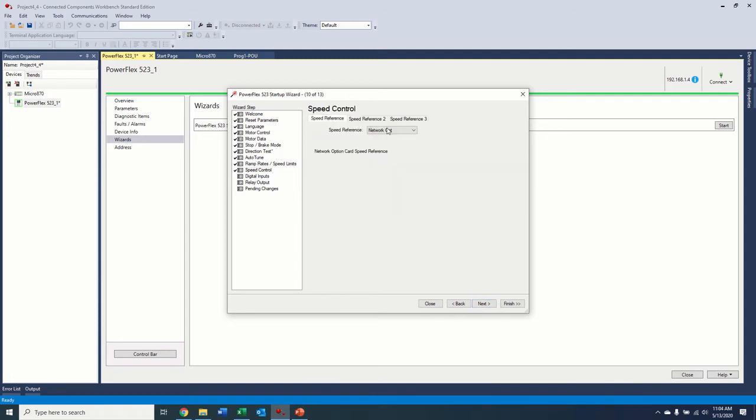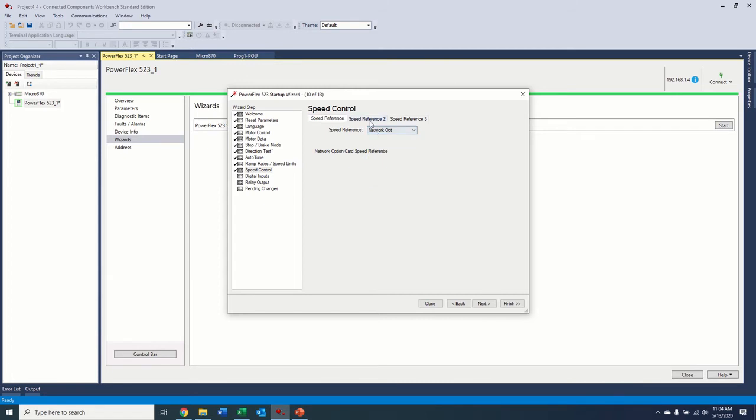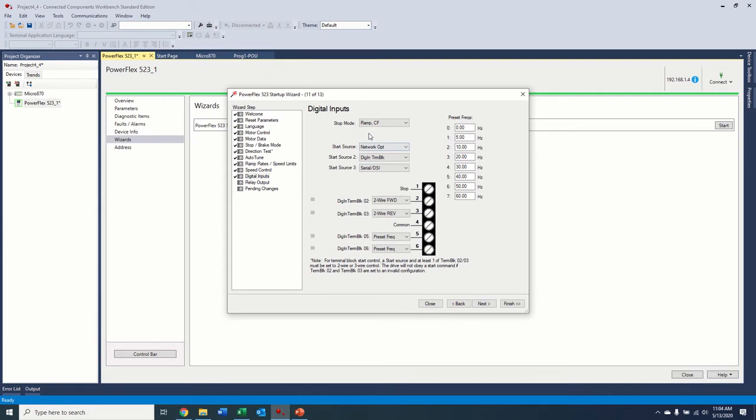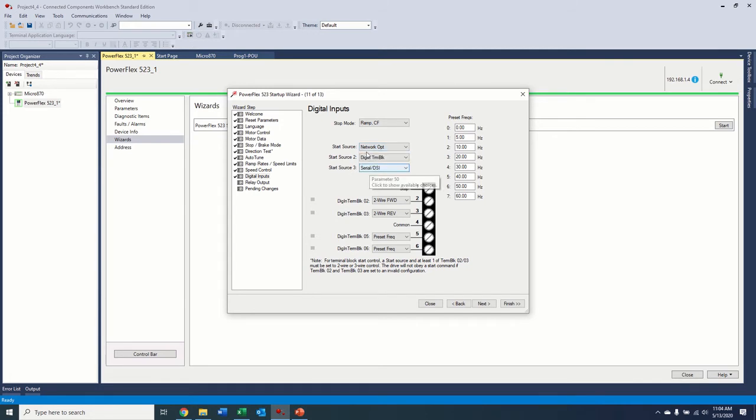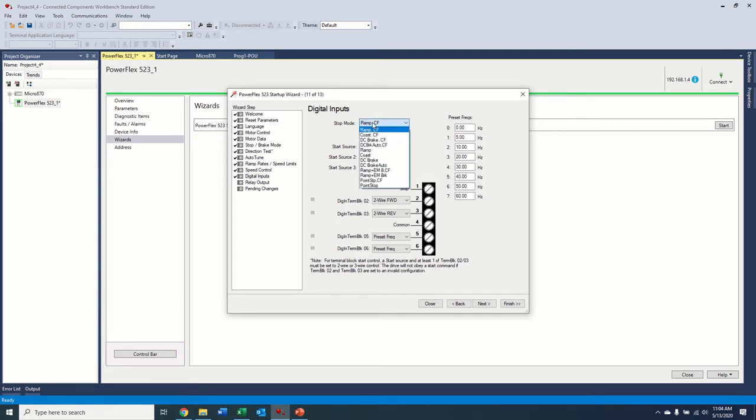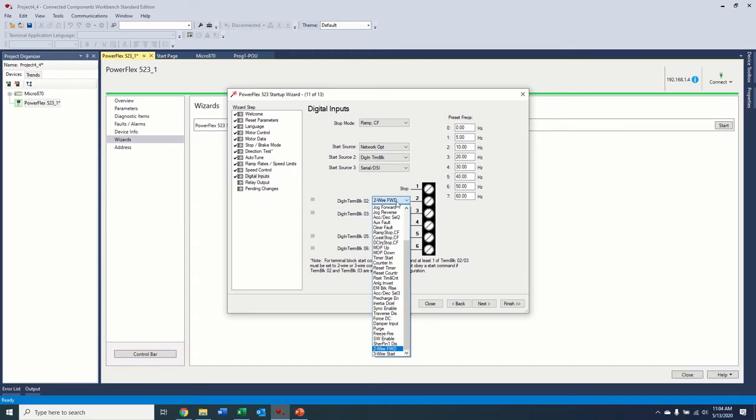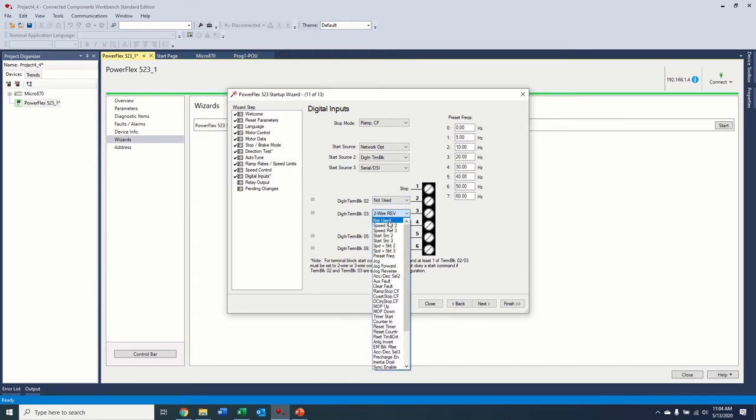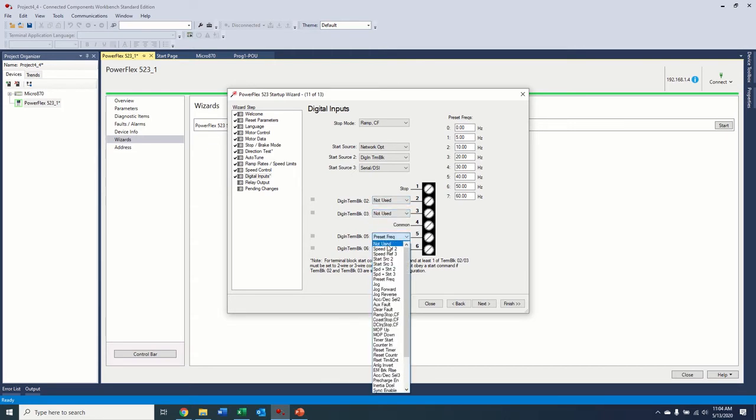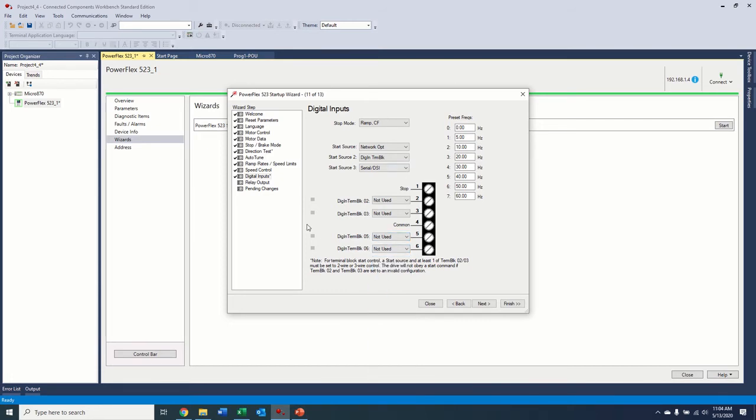All right, so our speed reference, we're going to leave this at network, because we're going to control this over the Ethernet. But if you wanted to control that from any of these, you would select that here, as well as your other three references, if you're switching between them. Our digital input. So here, our start source, I want to make sure that's at network. Because again, we're going to use the Ethernet to control this thing. We want to ramp or coast or brake for our stop mode. And then if we were using hardwired control, we could set all that up here. Or we could actually just set all these to not use. So just in case anyone tries to wire the drive up, it won't work.